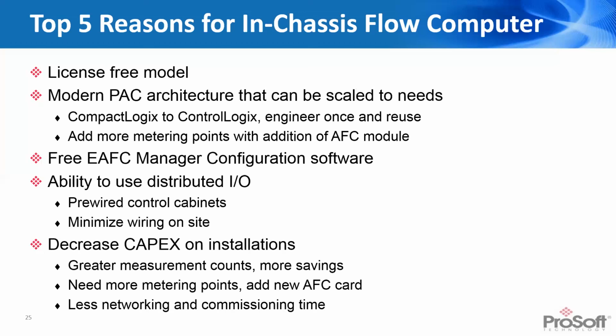The ability to use distributed I/O allows you to really take advantage of things such as pre-wired control cabinets that sit out near the separators and the tank batteries. It minimizes your overall wiring on site because you're not home running 16 pair wire that's going all the way back to the control cabinet. Instead, you're just running power and Ethernet, and you're wiring directly to things like distributed I/O blocks or point I/O out on site. And then really you get to decrease your CapEx on installations. And so the greater the measurement count, the more savings.